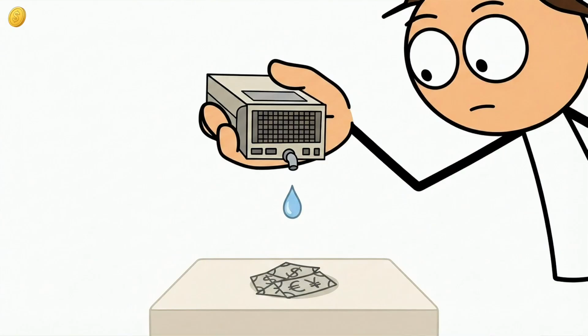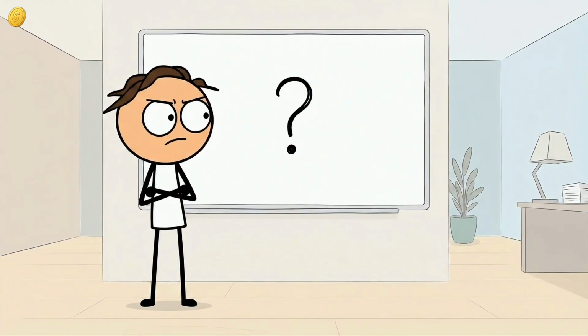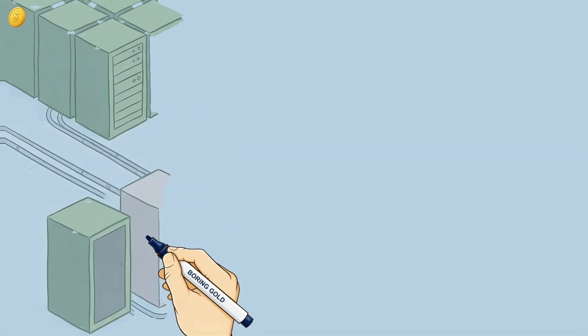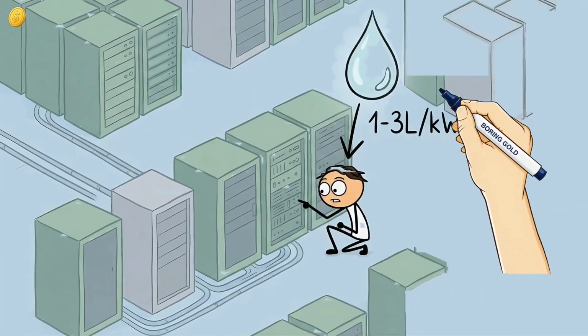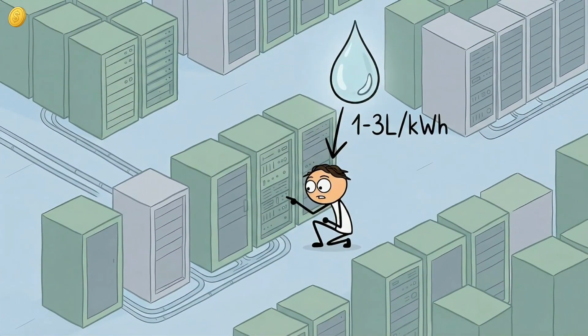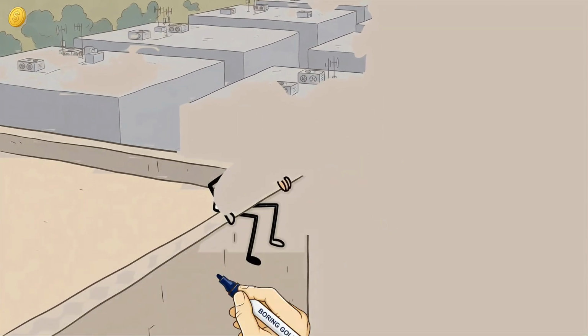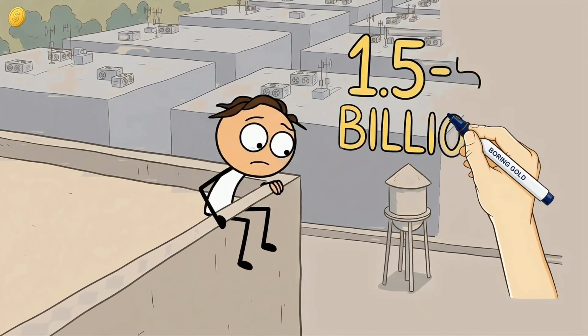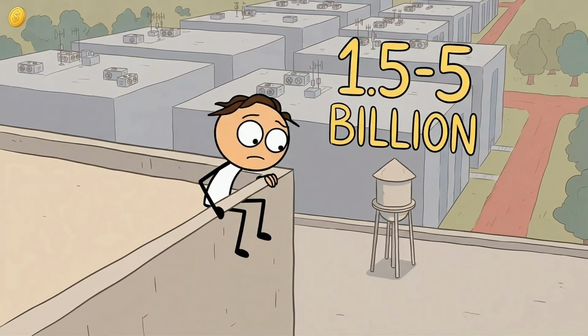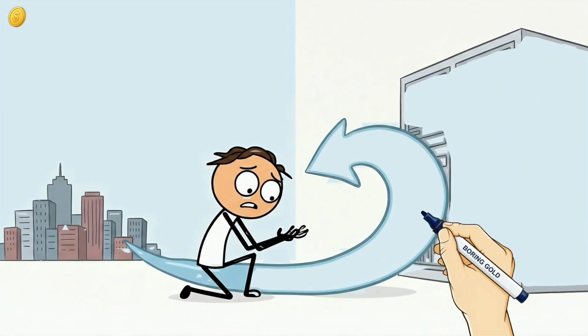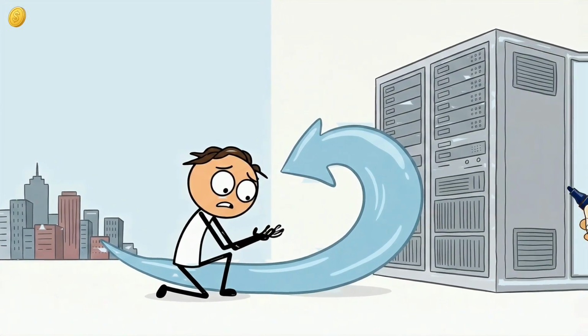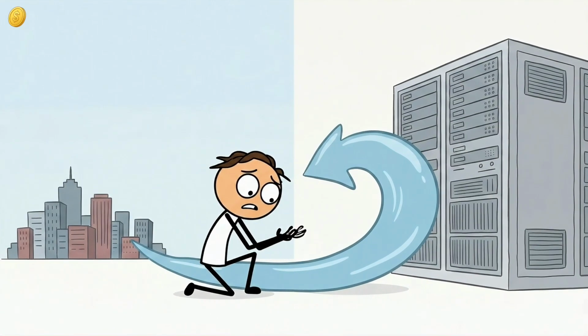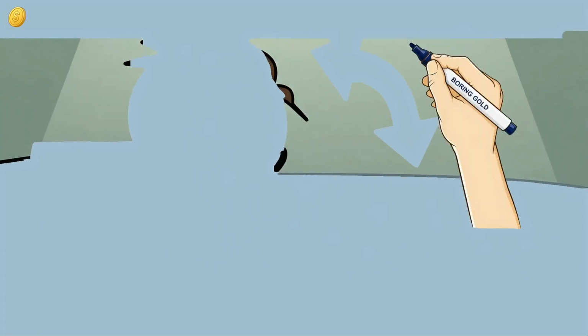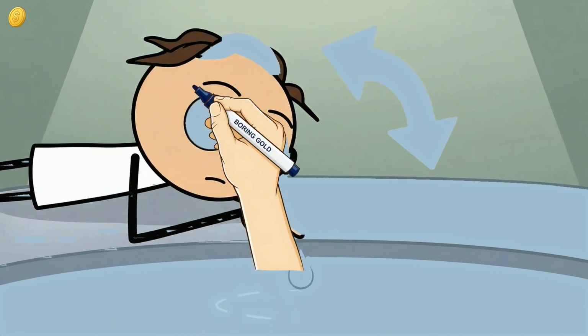Here is the number that tends to produce silence. A large, air-cooled data center using evaporative cooling towers can consume between 1 and 3 liters of water per kilowatt-hour of IT load. A 100-megawatt data center, a size that the largest hyperscalers now build routinely, can consume between 1.5 billion and 5 billion liters of water per year. A single large data center can consume as much water annually as a small city of 20,000 to 50,000 people. Read that again. Not a city's worth of electricity, a city's worth of water.